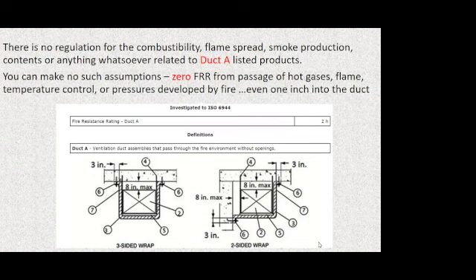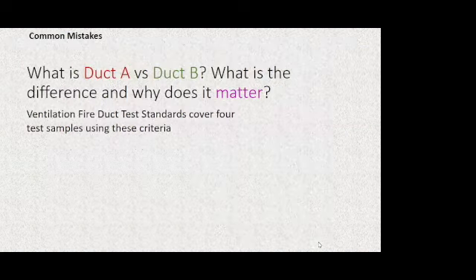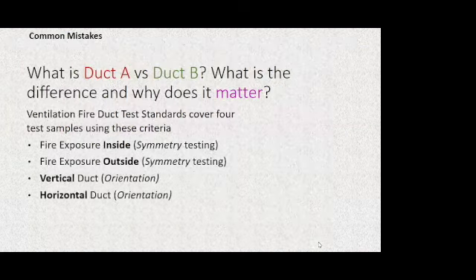And once you know the provisional limits of what was tested, you realize that this has no legitimate use whatsoever in the US-based code system. It's a test specimen born in Europe and the UK, where they have a totally different approach to fire-rated ducts, completely different than ours. Their concepts of fire resistance bear no resemblance to ours. And the fact is, in the US code system, duct A and duct B are merely test specimens from a test standard that tell us whether or not they did their testing on both sides and whether they used appropriately the lower of the two results, which is what we need to do according to our building code.